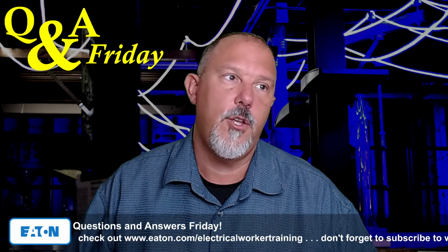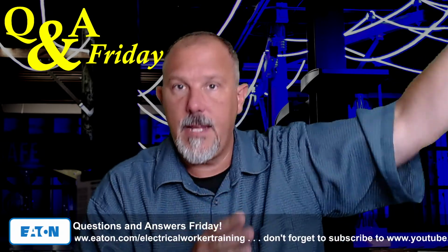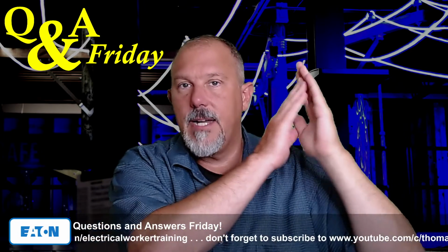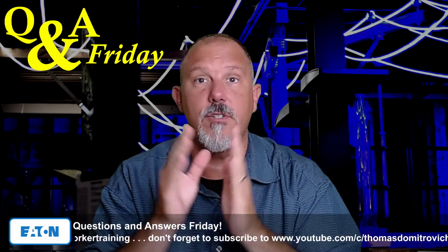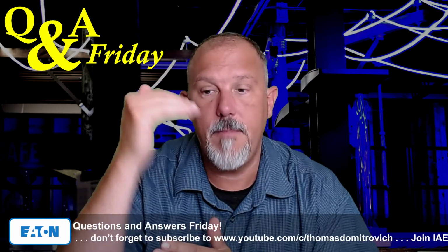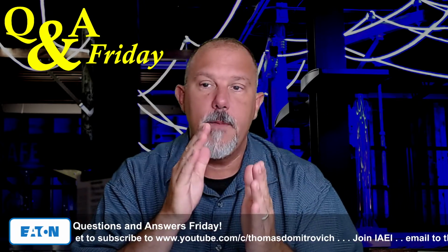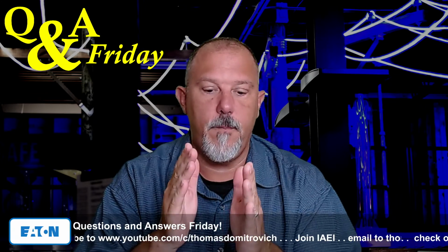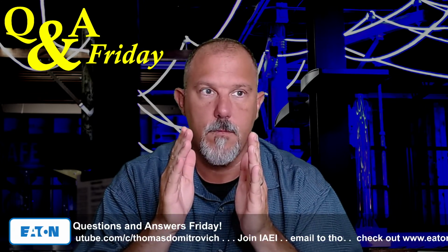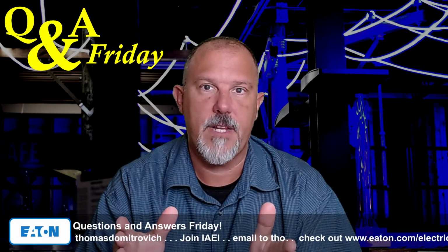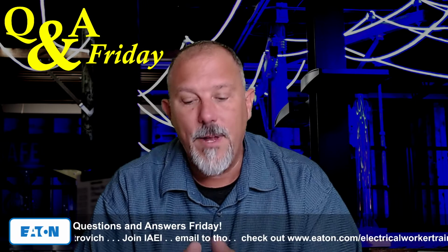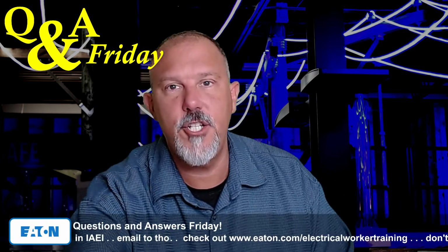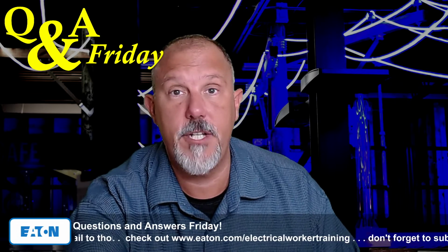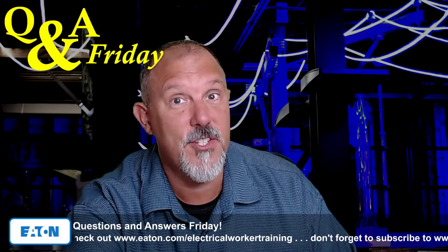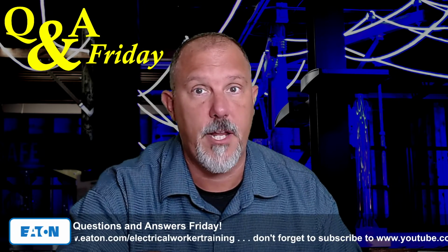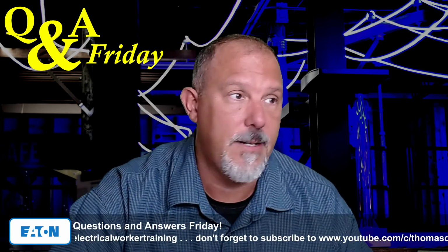I would say that some people will say, here is the line side if the clearing time is based upon the upstream overcurrent device, and then here's the incident energy for when the main overcurrent protective device clearing time. So the challenge there is to understand from a labeling perspective what is required, and then what is practical.